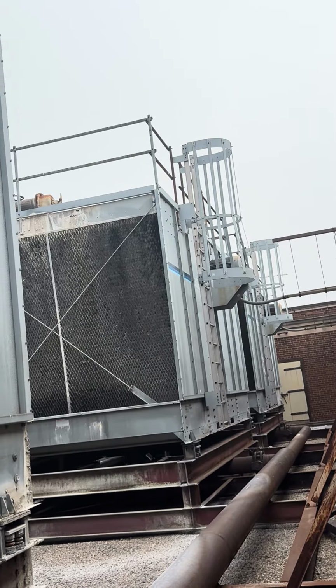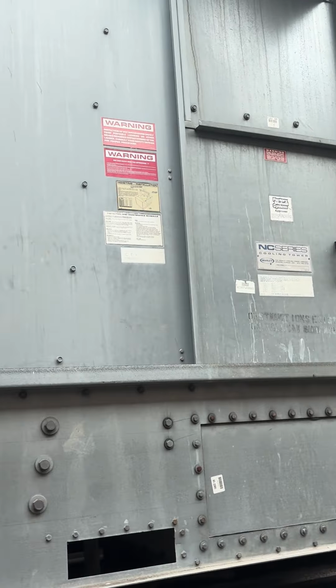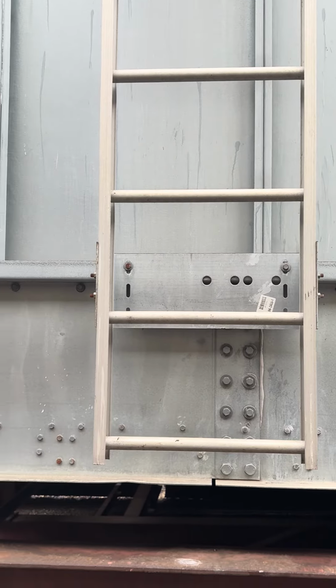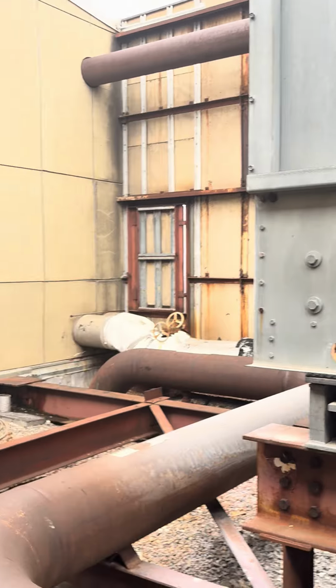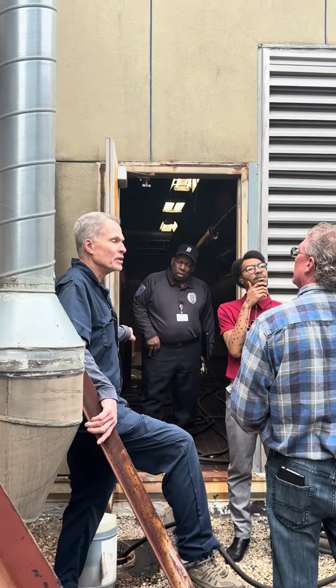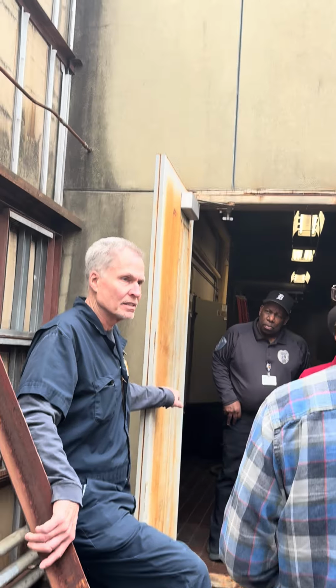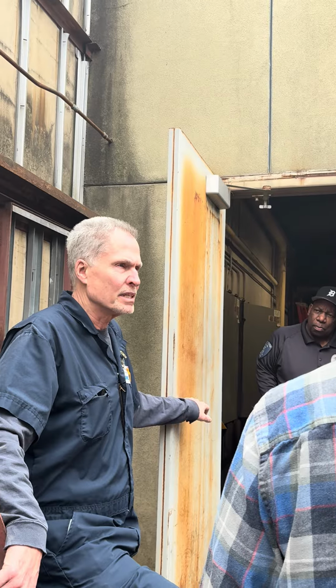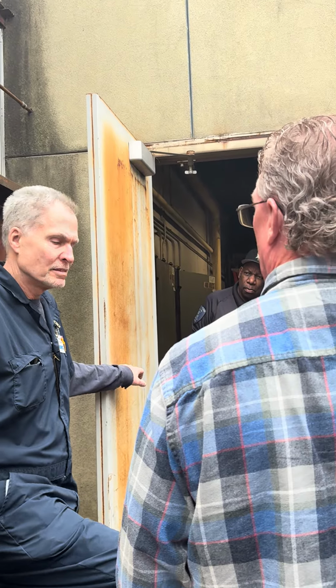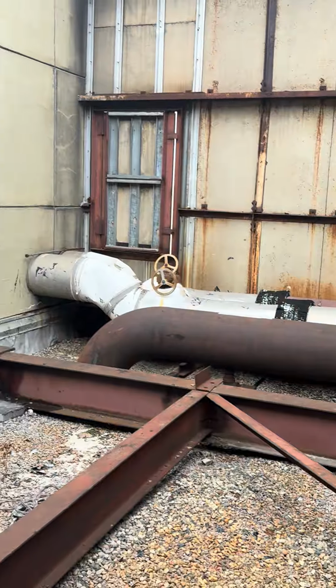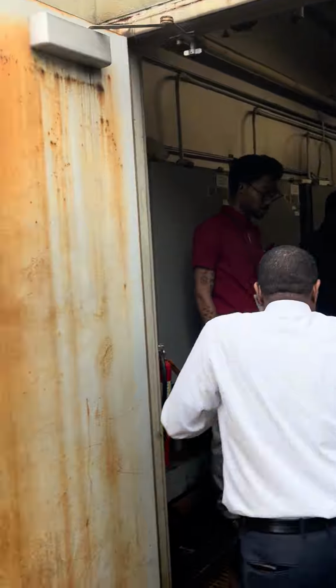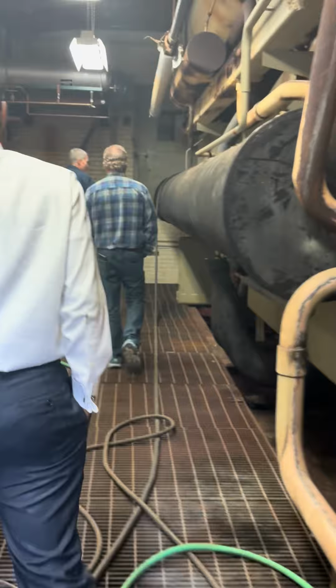How old are these towers? These towers were 90. And they're in bad shape. The ones on East Edition are real bad. You will not hit set point with two machines. They've been patched so many times, you can't patch them anymore. Sure. I get that. We're in a lot of those meetings. So this machine is 1,100 tons. It's actually putting out about 700.